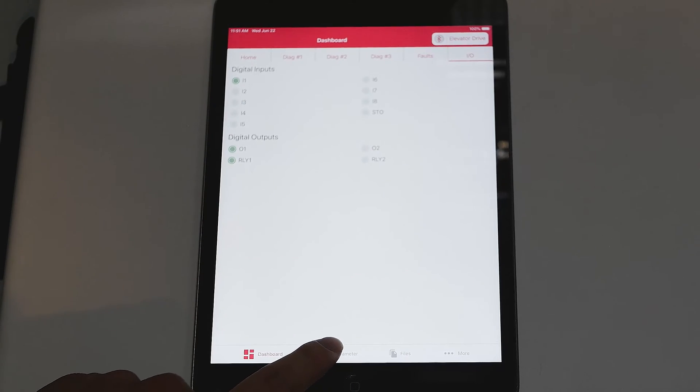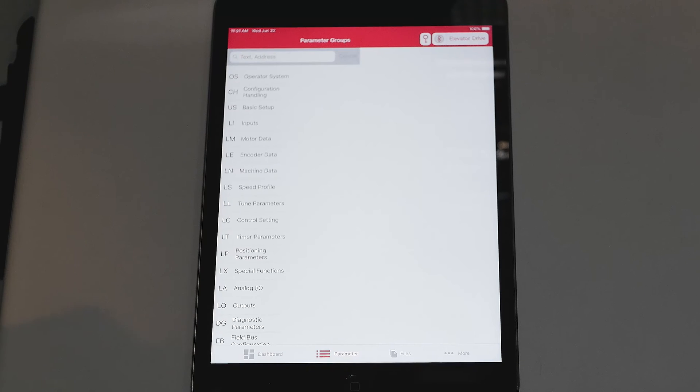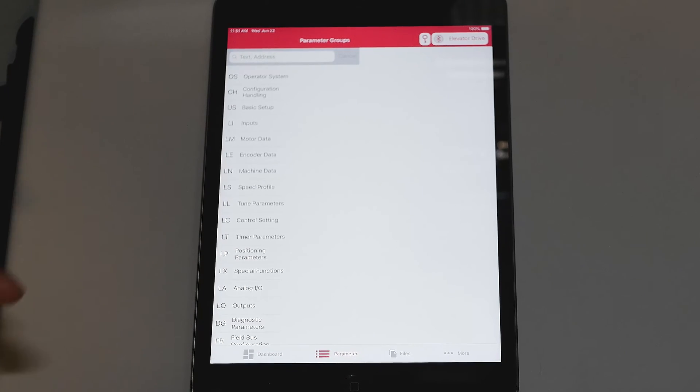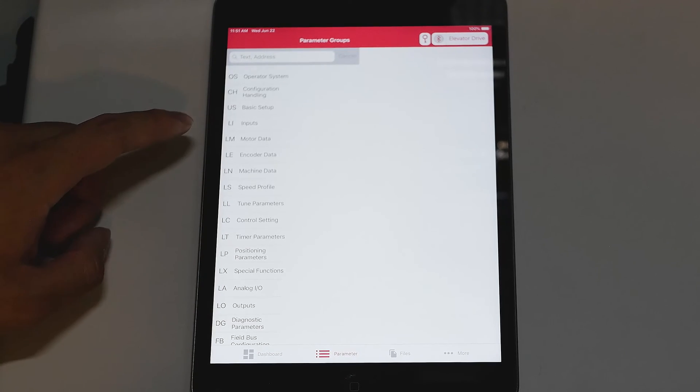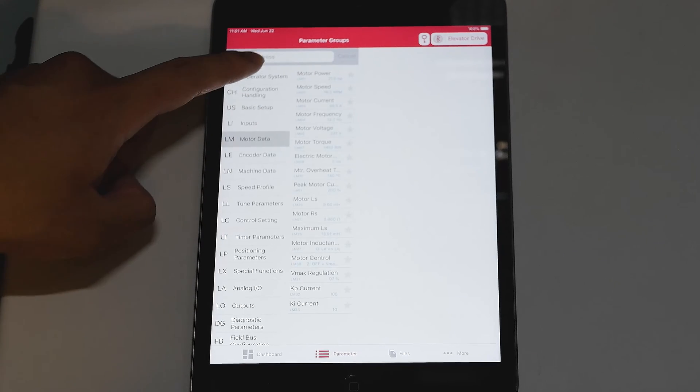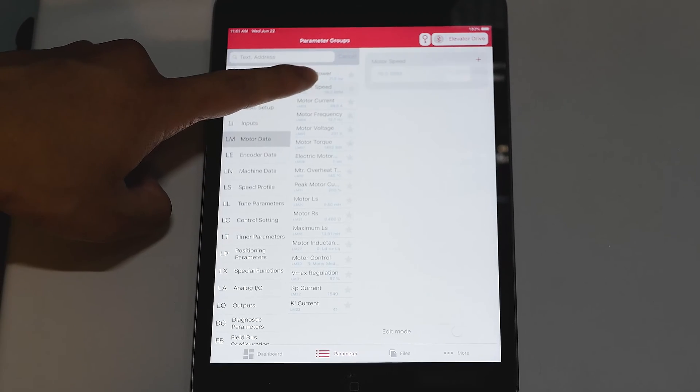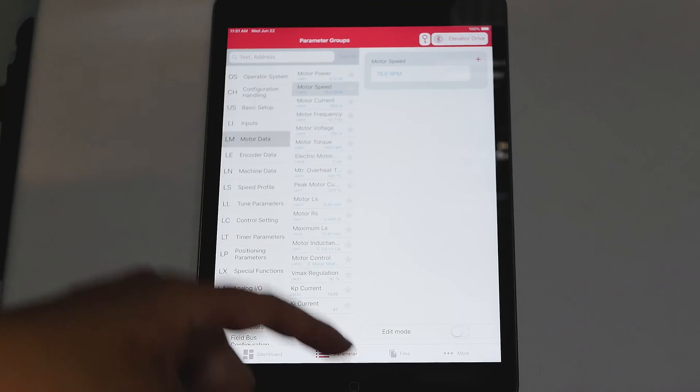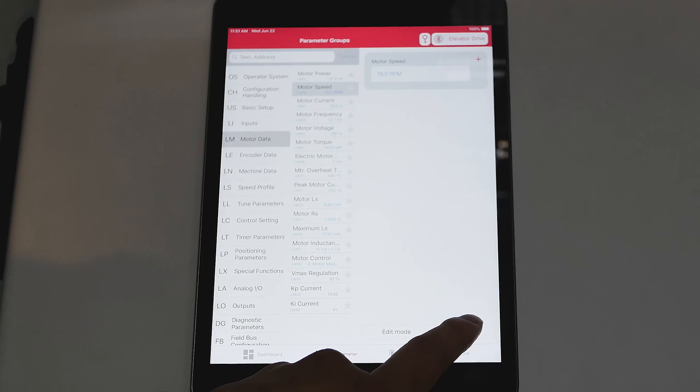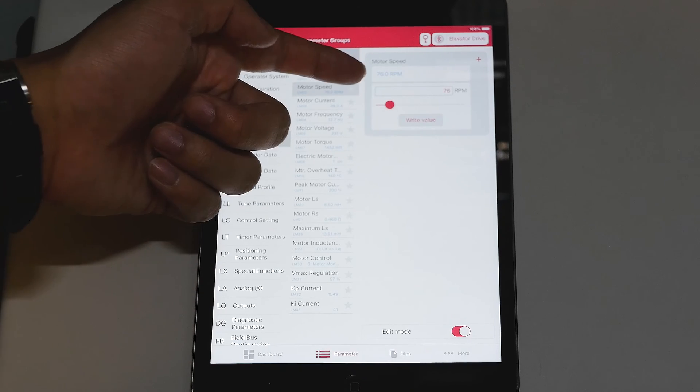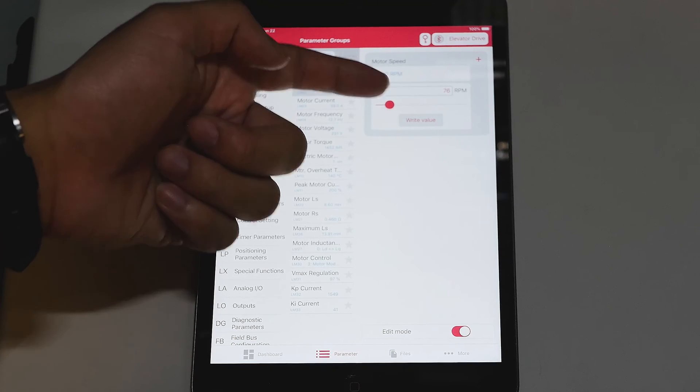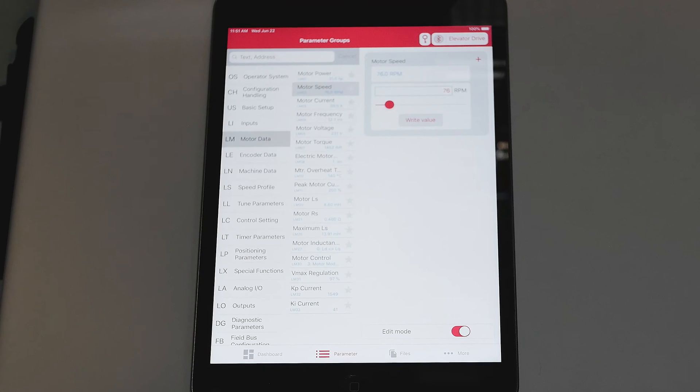You can also go to parameters and make any parameter changes you need right on your device. For example, if you want to go to motor data, change motor speed. You go to edit mode and then you would type in whatever your value you want as your RPM and click write value to save it and this will write it right to the drive.